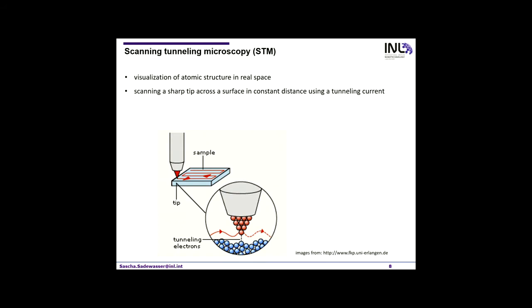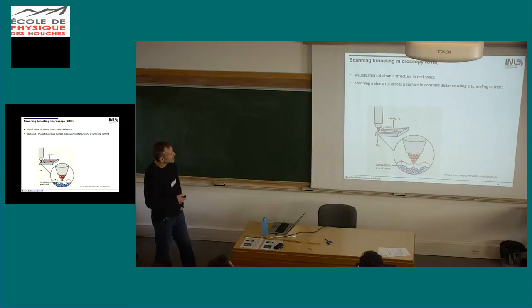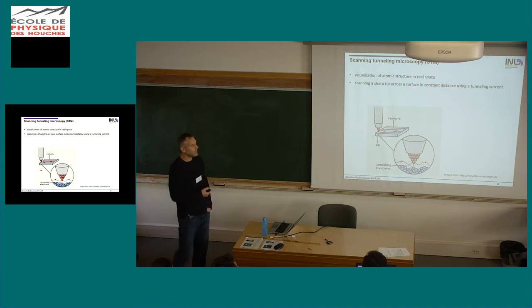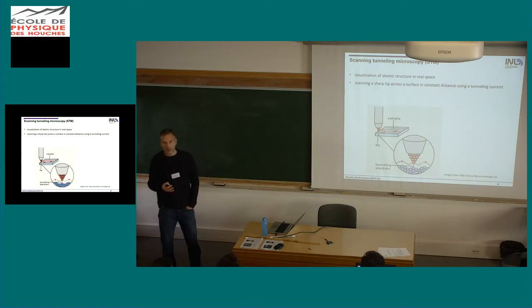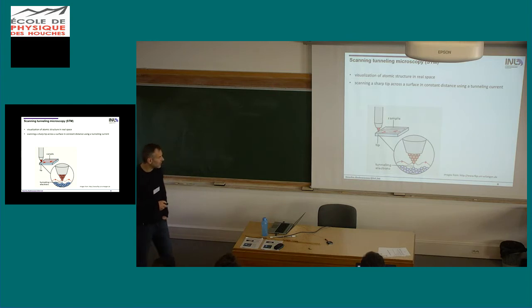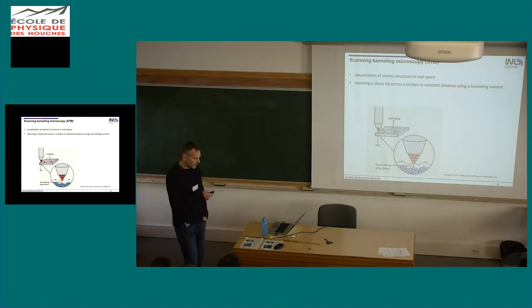So how does it work? We are visualizing the atomic structure in real space, and this was the first time it was actually possible to do that, with the scanning tunneling microscope. What we do is use a very sharp tip, atomically sharp ideally, and scan it across the surface. It's similar in some sense to a record player. Again, this goes back to maybe before the lifetime of some of the people in the audience. We keep the tip at a specific distance to the surface and thereby scan the surface morphology.